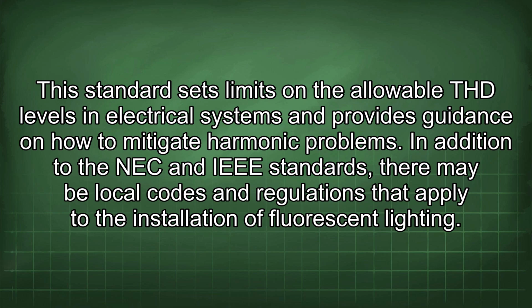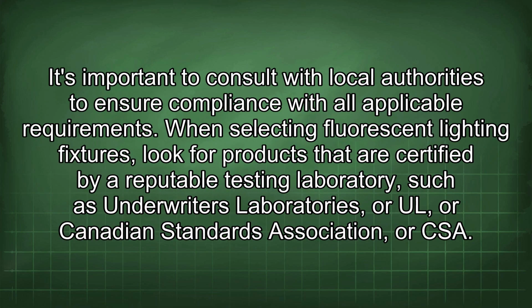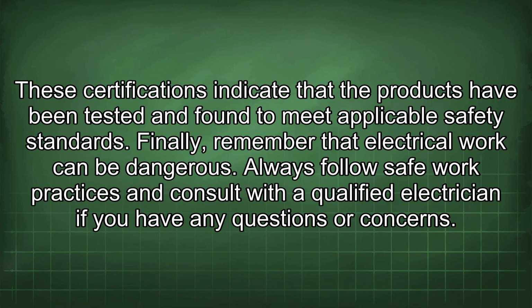In addition to the NEC and IEEE standards, there may be local codes and regulations that apply to the installation of fluorescent lighting. It's important to consult with local authorities to ensure compliance with all applicable requirements. When selecting fluorescent lighting fixtures, look for products that are certified by a reputable testing laboratory such as Underwriters Laboratories, or UL, or Canadian Standards Association, or CSA. These certifications indicate that the products have been tested and found to meet applicable safety standards.